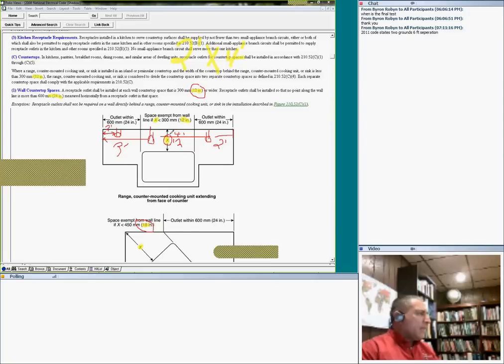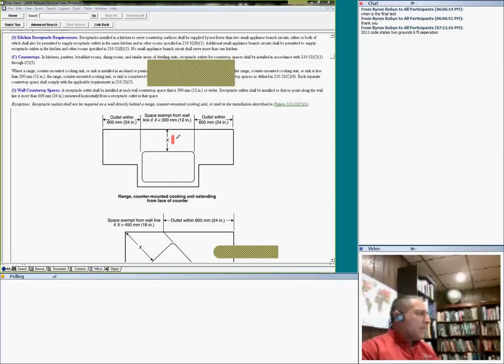If it's under 18, you count it. What does that mean, Chad? Suppose that this one is less than 18. Suppose that was 11 feet, guys. Then all I need is 1 receptacle here and 1 receptacle in this area. If it's 11 inches, no need for an extra receptacle. Then when you make this one 12, then you need the receptacle. Then in this area, you need a receptacle right behind it.